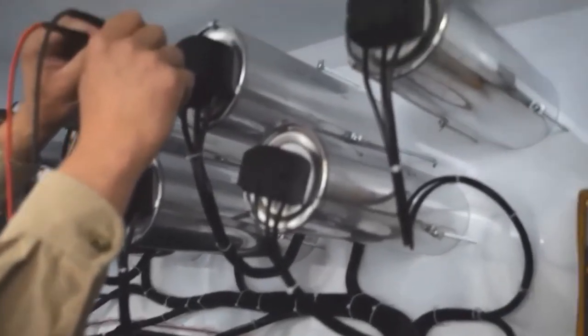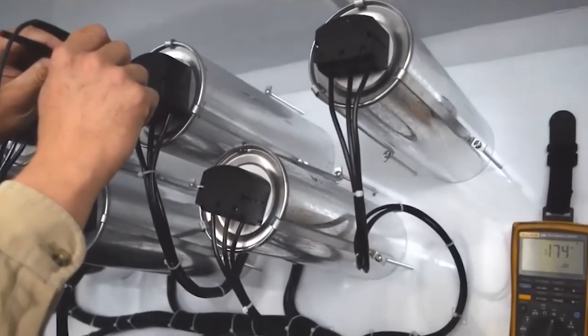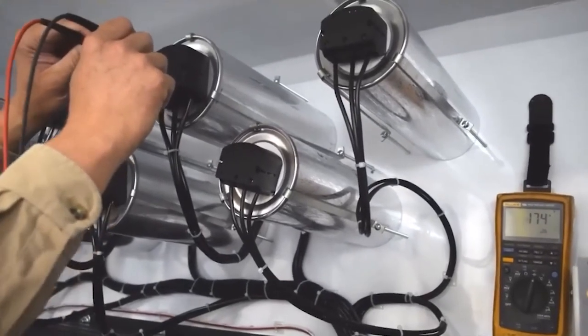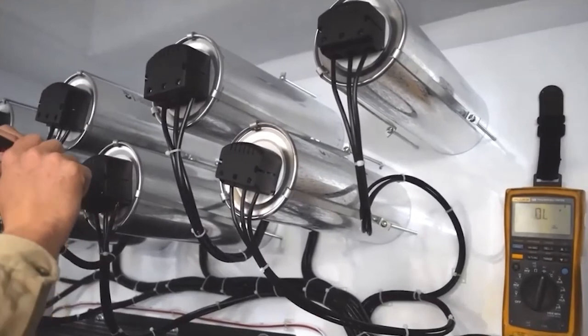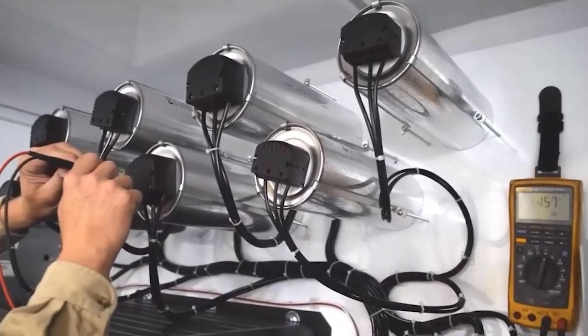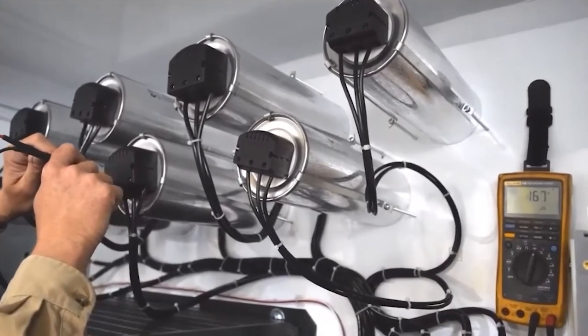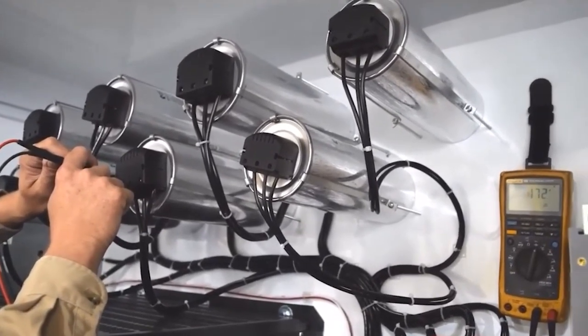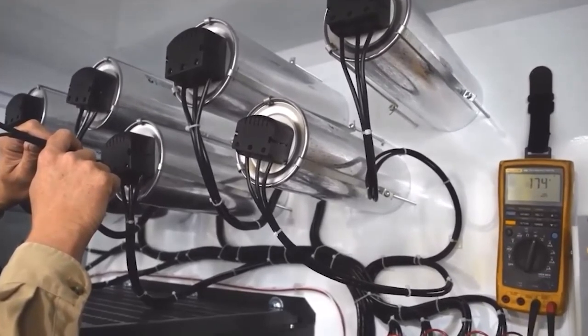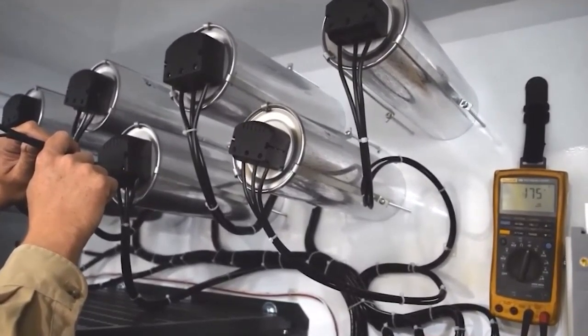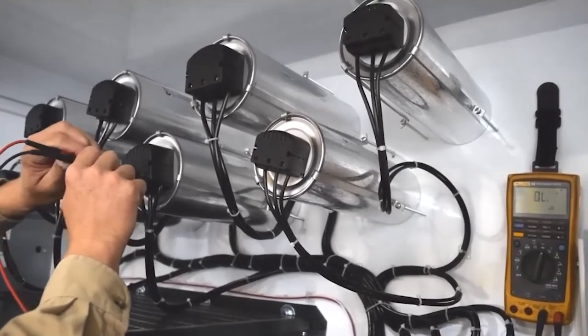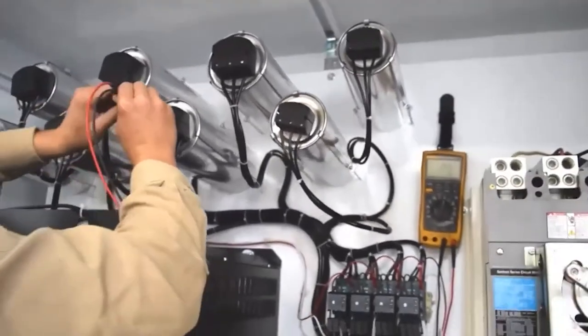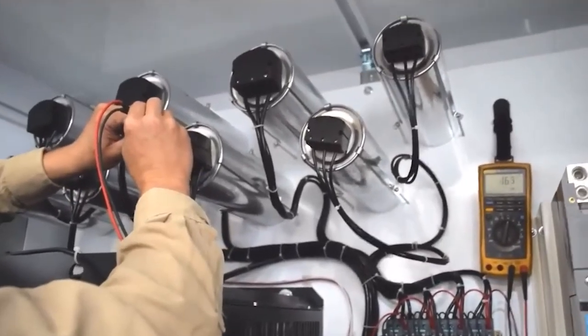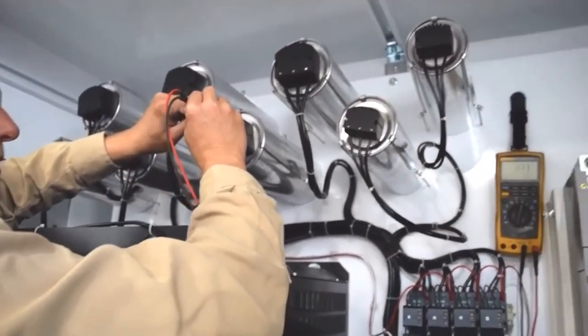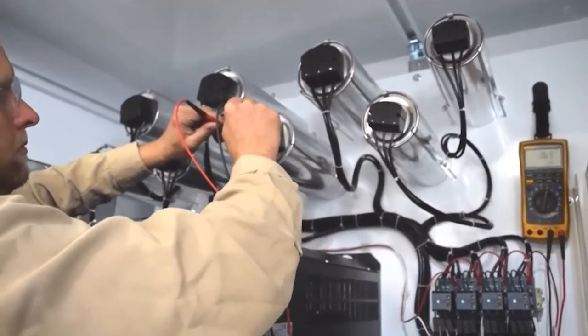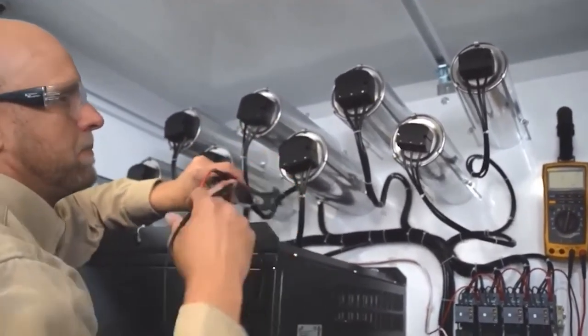One of the things I want to re-emphasize when I'm doing this is that you always want to isolate your caps, because you could pick up weird readings from the other caps if you don't, because they're all put in the circuit in parallel with each other. So if you don't isolate the capacitors from each other, you might pick up something from one cap that you're thinking is part of the cap that you're measuring. So we've gone through and measured it. For time's sake, this is where I stop going through the capacitors, but if you're doing a test in the field, you're going to continue on and test every one of them the same, verify that they're all okay.